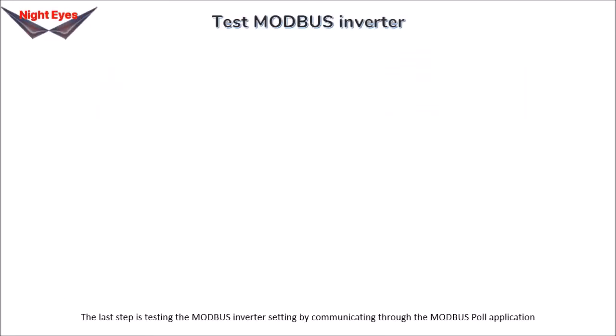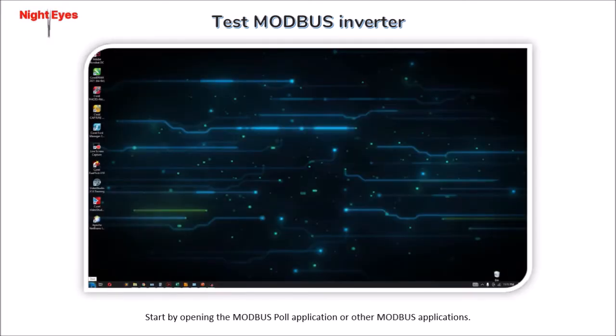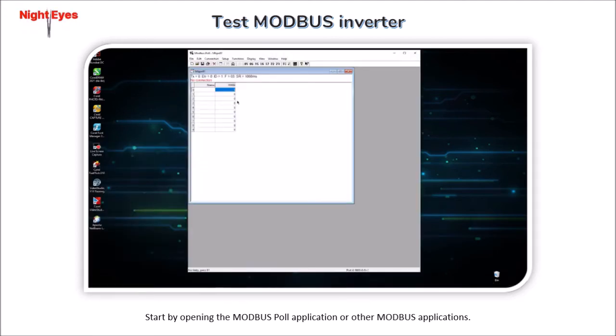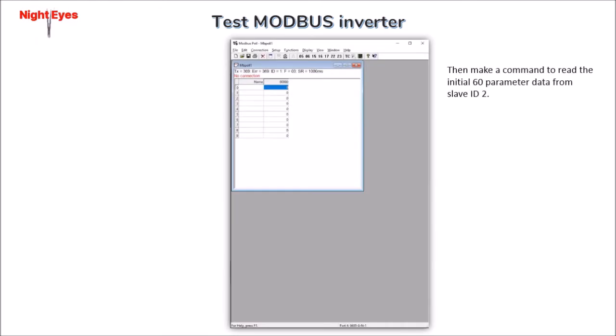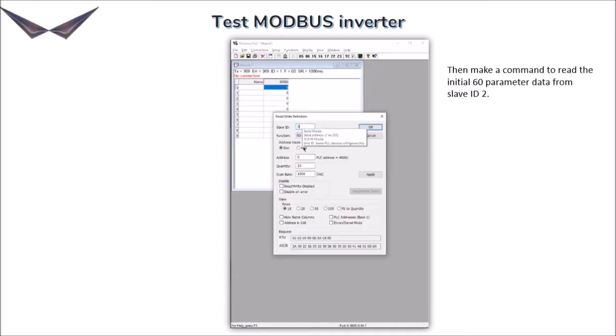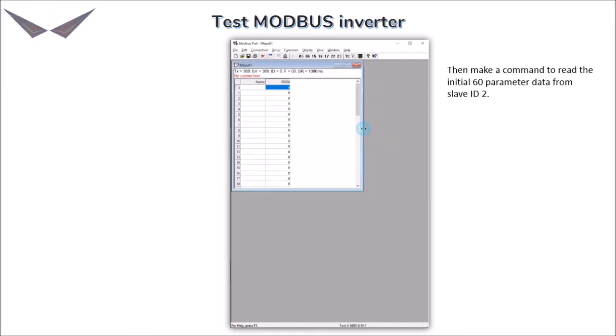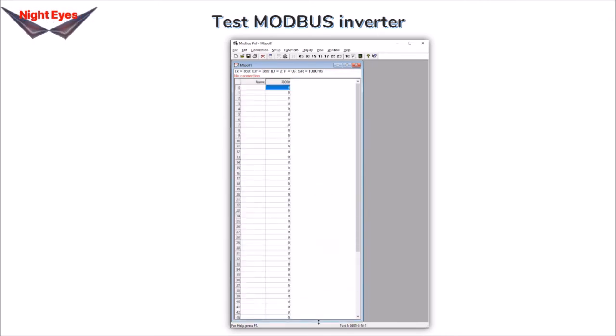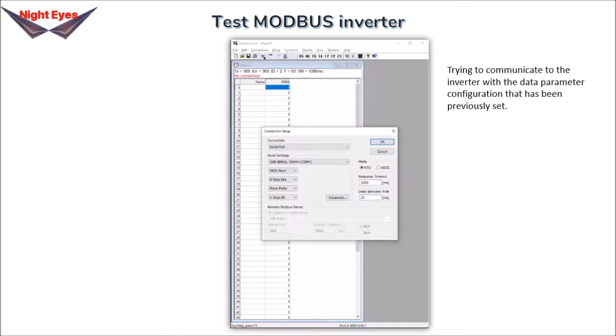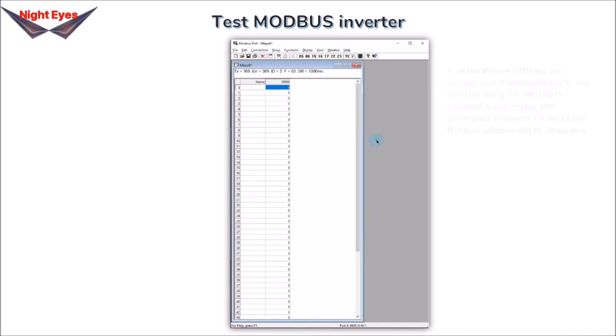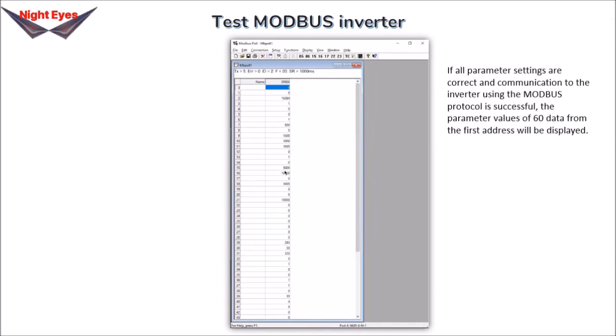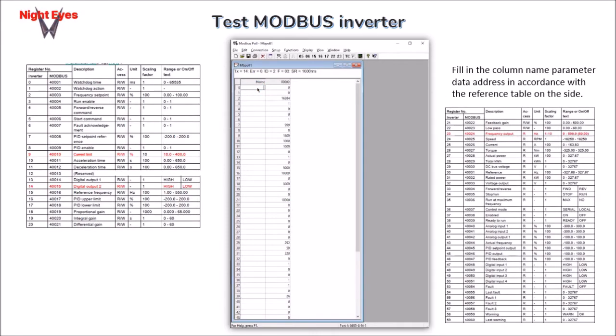The last step is testing the Modbus inverter settings by communicating through the Modbus Poll application. Open the Modbus Poll application, then make a command to read the initial 60 parameter data from Slave ID 2. Attempt to communicate to the inverter with the configured data parameters. If successful, the parameter values of 60 data from the first address will be displayed. Fill in the parameter data address column according to the reference table.